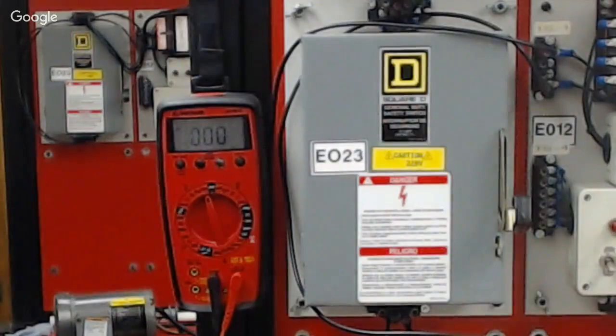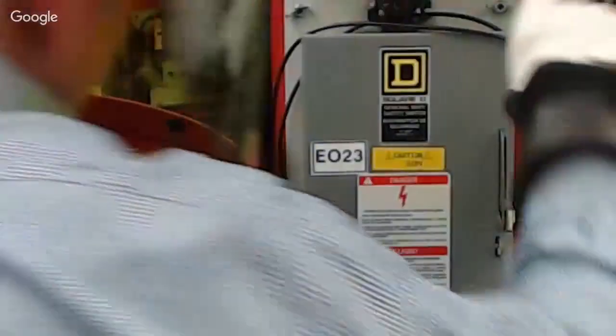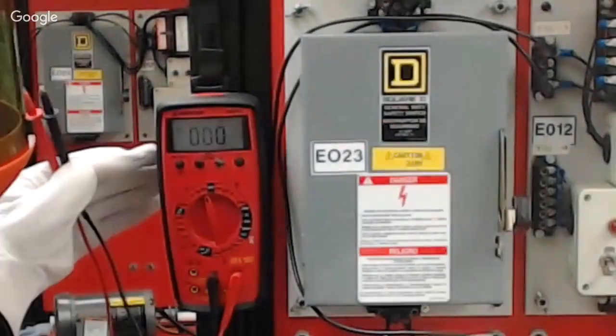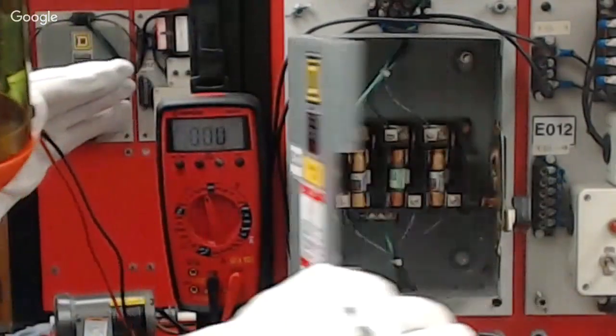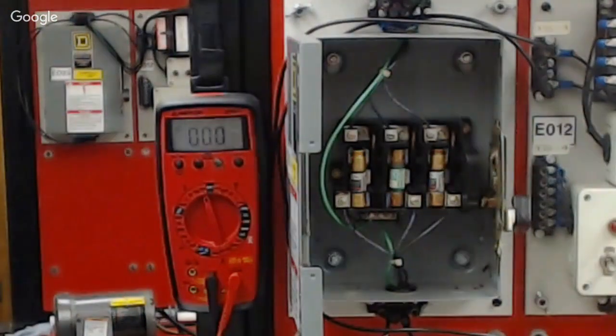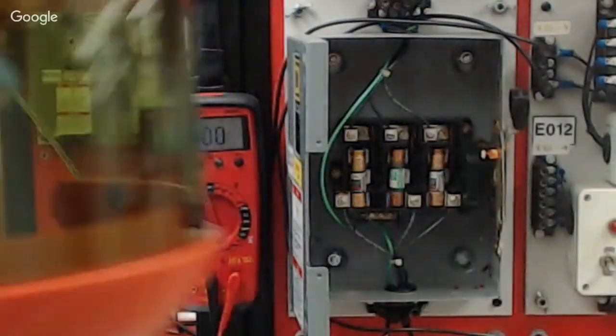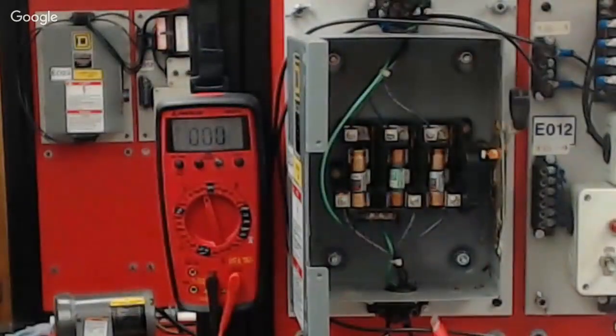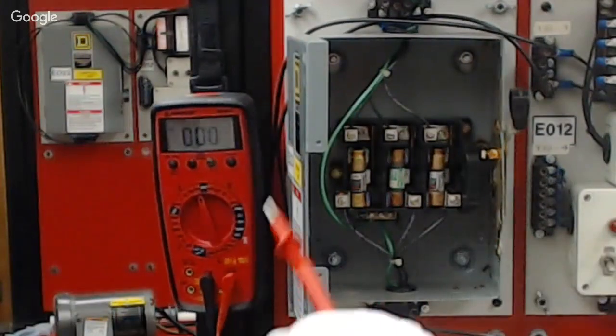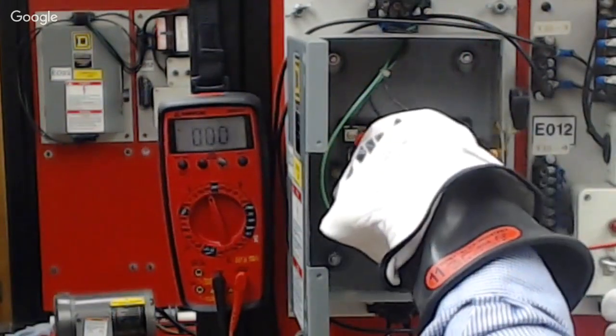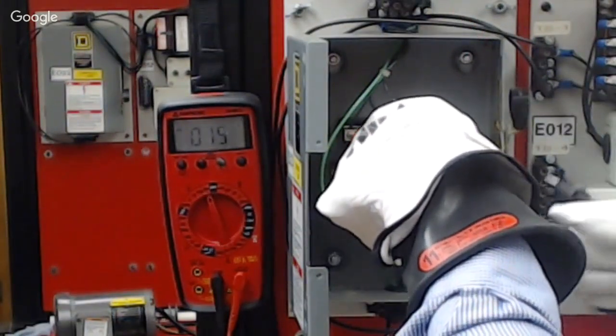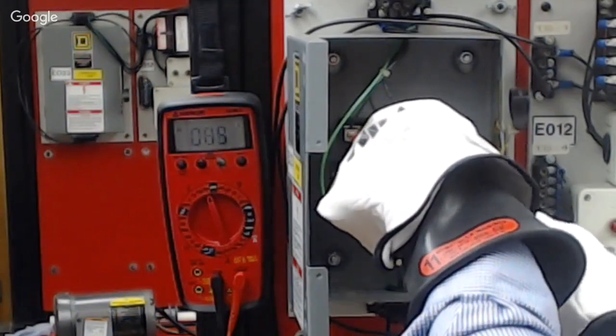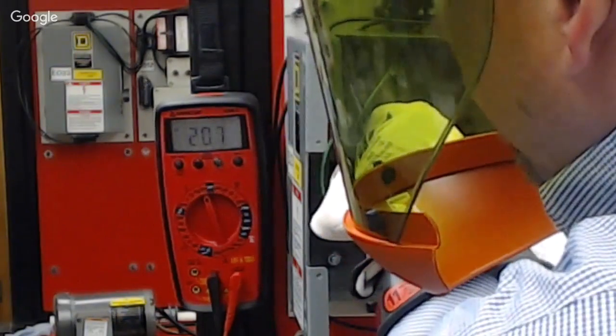So I'm going to energize this circuit, and I have my disconnect off. We're going to open the door. We're going to engage the circuit and use the cross-check method to check our voltage. So starting on the source side of L1 to the fuse side of L2, I'm going to check my voltage, and I'm reading 208.